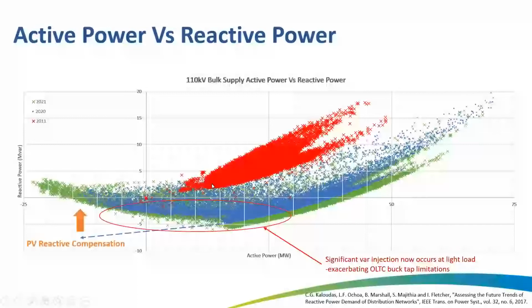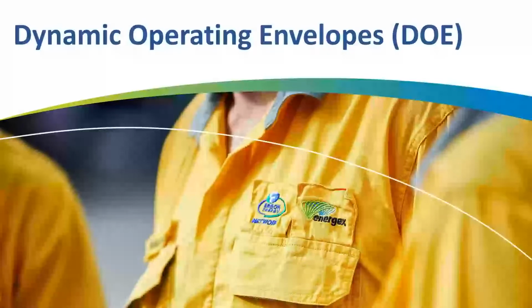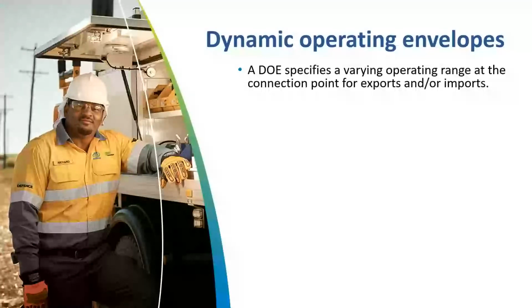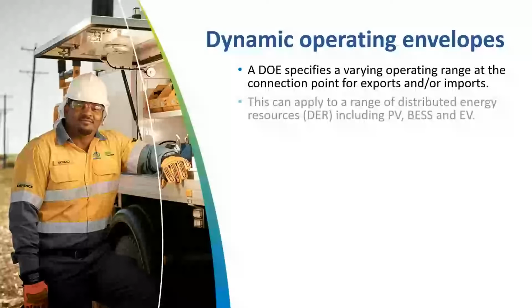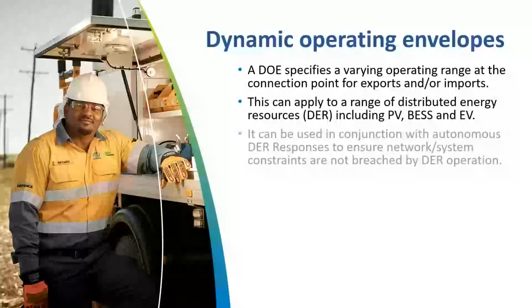So now, the whole point of our presentation: dynamic operating envelopes. We've defined a dynamic operating envelope, although there's still work going on to have a consistent definition nationally, as a varying operating range at the connection point for exports and imports. This can apply to a range of distributed energy resources, including PV, batteries, and electric vehicles. It can be used in conjunction with autonomous DER responses, such as the volt-var response that I mentioned earlier, to ensure network and system constraints are not breached by DER operation.